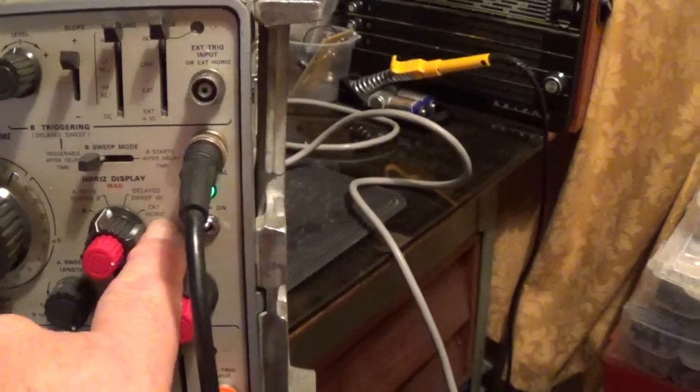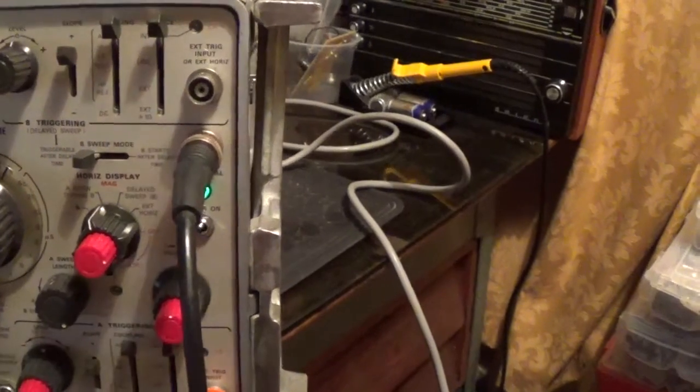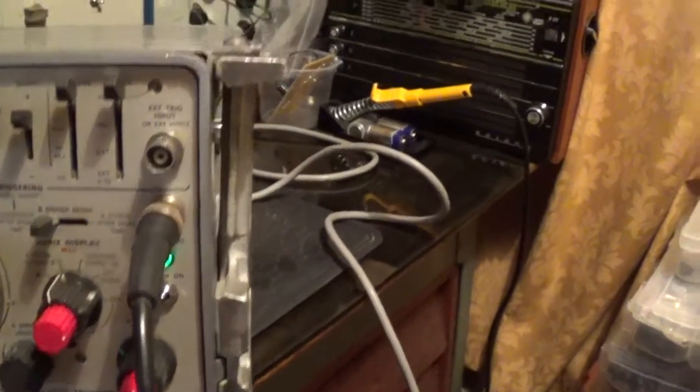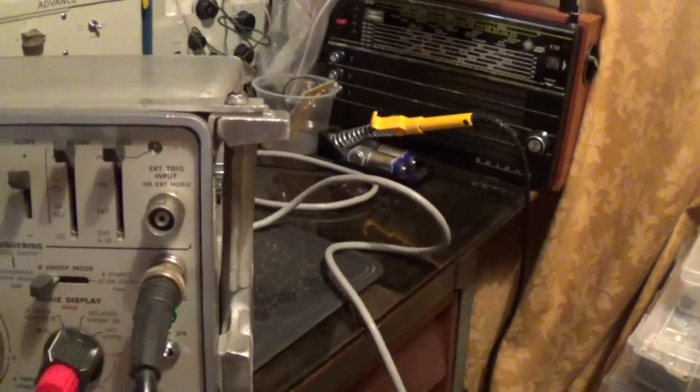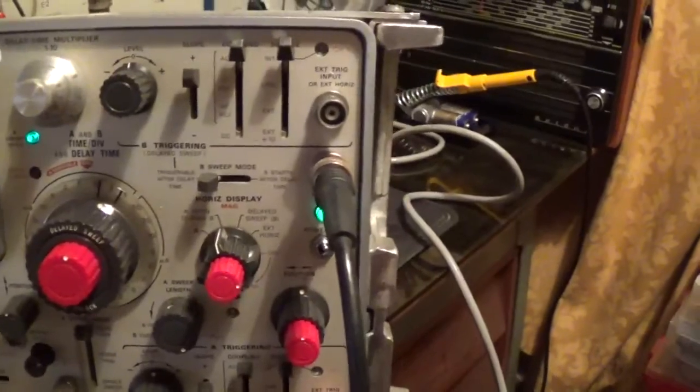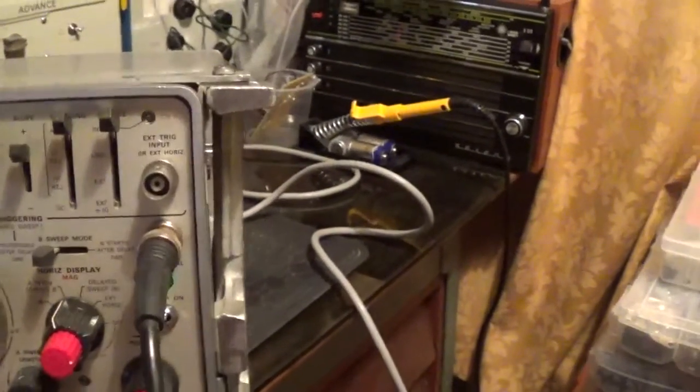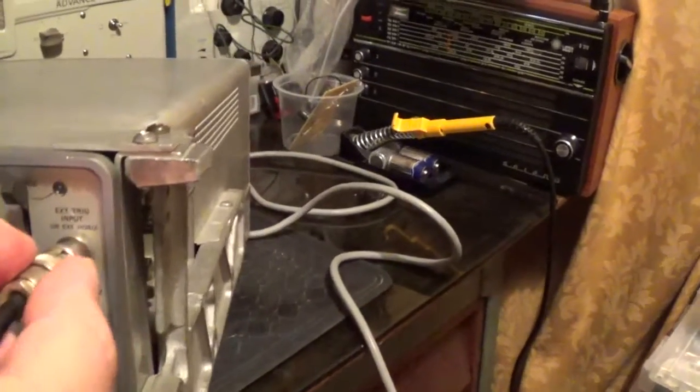The external horizontal position is here, and the input is into here. Took me a while to figure that out actually, but let's have a look at it. We've got the calibrator connected up. I'm going to connect that to the input.